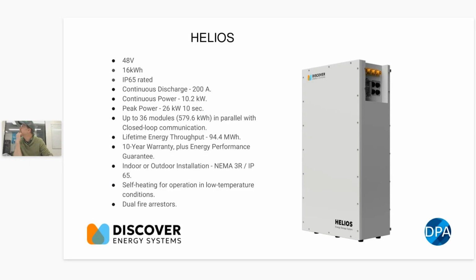Does everybody understand that? What temperature is cold? Negative 15 is too cold to discharge, and I think below 5 is too cold to charge. But in practice, the thermal mass of these batteries means most batteries in Australia are very unlikely to get below 5, even if ambient temperature is down there. The actual thermal mass of the battery isn't going to get there very easily, so it's not a problem we see very often.